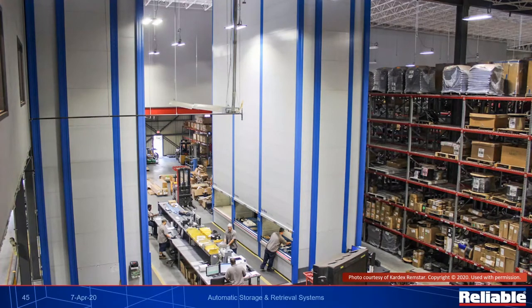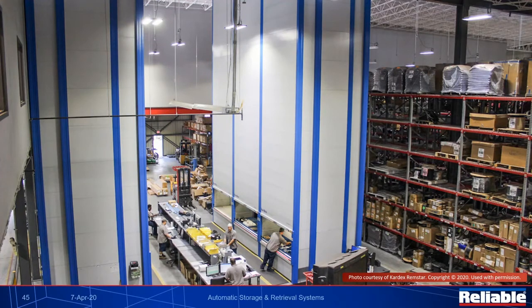What's interesting, and it's unclear to me how this works out in the real world, and if anybody has any guidance, you can put some comments to us in the chat. This document says that you shall calculate all the sprinklers in the units. And when we look at these units that are put together side by side like this, there's really no differentiation. There's no walls anymore. So this is, in essence, I think, an all open unit inside of there. And does that mean you calculate all three of one of these units' sprinkler heads? Don't really know. It's one of those things that the data sheet is a little bit vague on. And that means that the FM reviewer or the AHJ can probably latch on to that ambiguity and then force you to end up calculating more sprinklers than you had possibly anticipated in this type of arrangement.